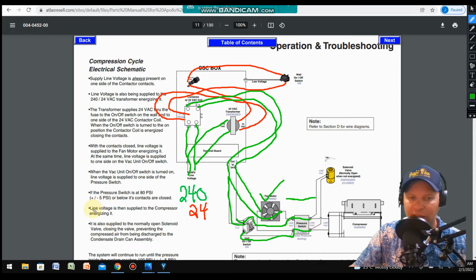Hopefully that makes sense. Line voltage is then supplied to the compressor, energizing it. So this is basically just going to go through here to your compressor, turning it on. So just to kind of show you, the line voltage basically is making it through all of this, through here, through this switch, through the pressure switch, and then to the compressor. So you're beginning to see a path. And this path, understanding this path is really important for troubleshooting, because this is what allows you to divide the system up.